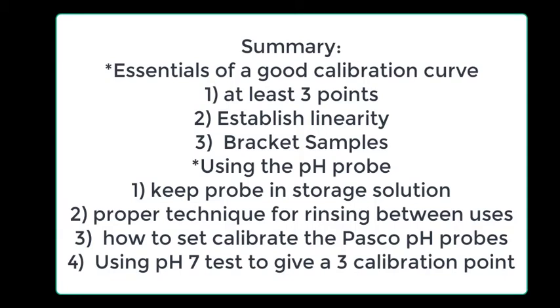So today we were able to look at the essentials of a good calibration curve that it should have at least three points. You saw ways to establish linearity with using your R-squared factor. You learned to bracket samples and put high and low calibration samples around where you're going to actually be sampling in the lab. Then we broke off and talked about using the pH probe, how that you want to keep that pH probe in a storage solution that has an equal ionic strength of what's inside the pH probe itself. That way the solution that's in the probe won't leach out. We talked about proper technique for rinsing between uses, how to calibrate the PASCO pH probes in particular. And then we showed you how in an academic world you could use a pH 7 to give you a third point on a calibration curve. And I hope this helps. See you in the lab.